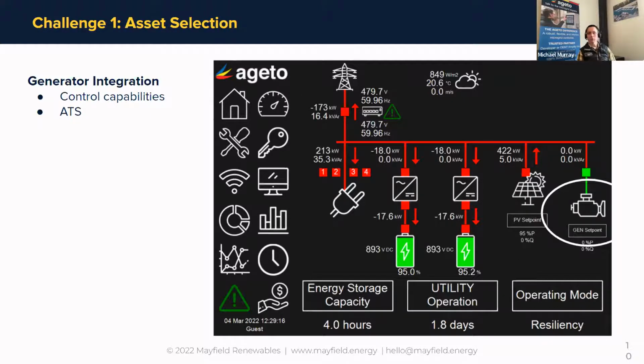So typically what we're pushing for in these microgrids is a seamless integration. That's where we want the generator to be able to parallel and synchronize to the microgrid bus. This will allow the microgrid controller to tell exactly how much power is needed, similar to what we do with the solar inverters and the energy storage system. So more and more generator companies are fitting generator controllers to their gen sets that can have this functionality. It's typically a $5,000 to $10,000 upgrade on the generator for this paralleling capability, but it greatly increases the functionality of the microgrid.